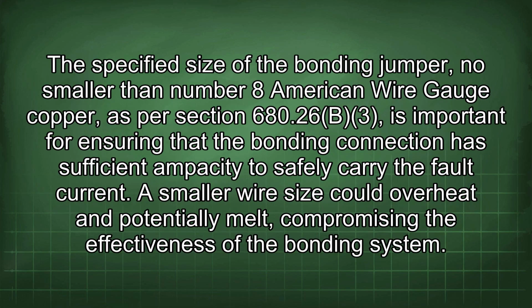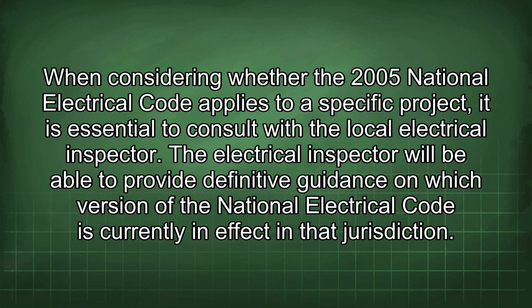The specified size of the bonding jumper, no smaller than number 8 American wire gauge copper, as per Section 680.26(B)(3), is important for ensuring that the bonding connection has sufficient ampacity to safely carry the fault current. A smaller wire size could overheat and potentially melt, compromising the effectiveness of the bonding system. When considering whether the 2005 National Electrical Code applies to a specific project, it is essential to consult with the local electrical inspector. The electrical inspector will be able to provide definitive guidance on which version of the National Electrical Code is currently in effect in that jurisdiction.